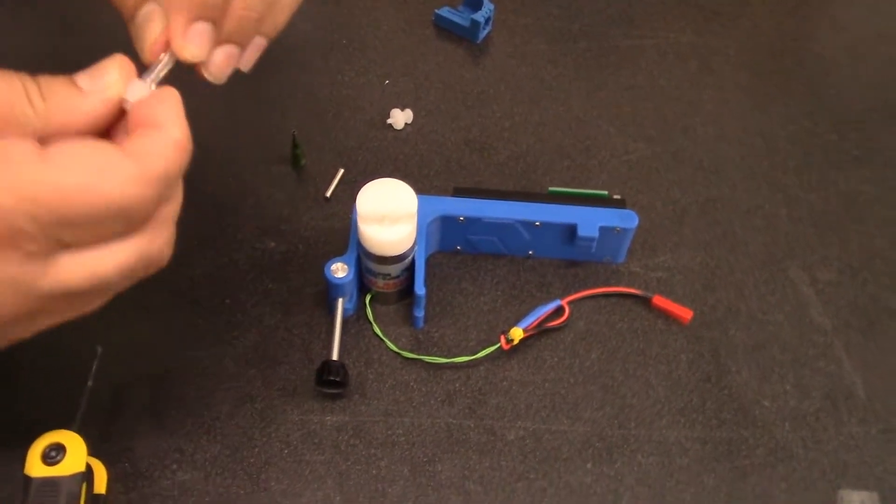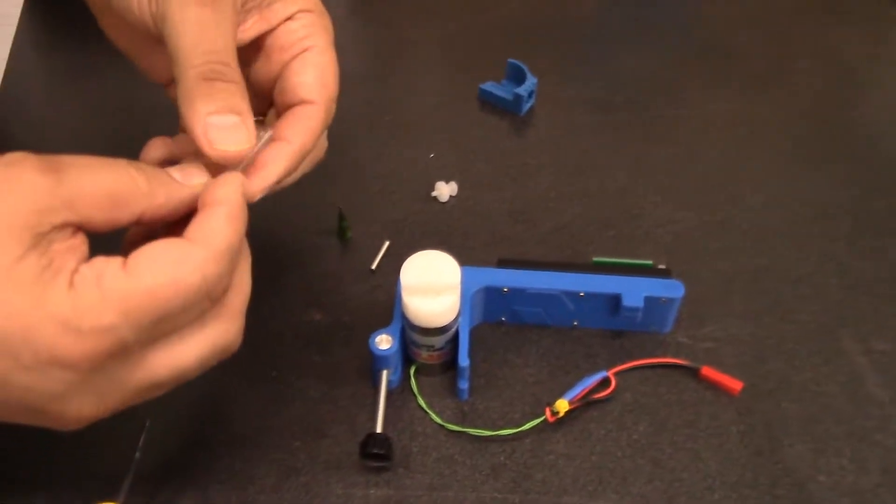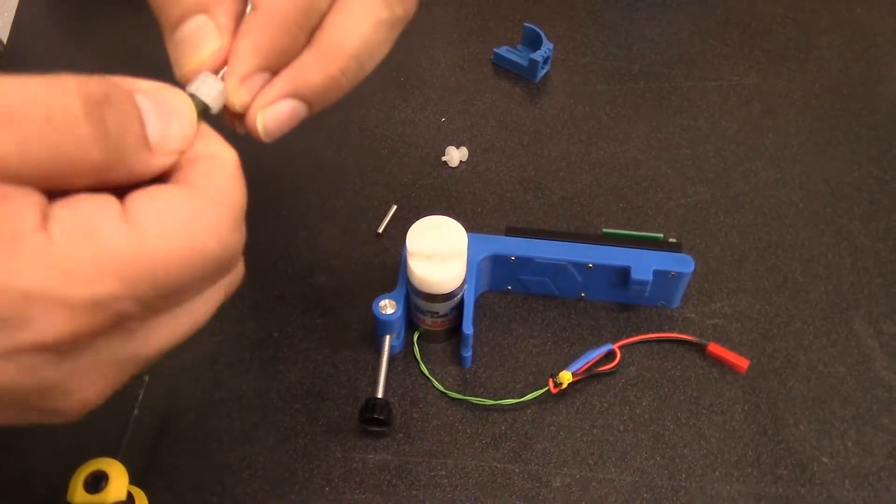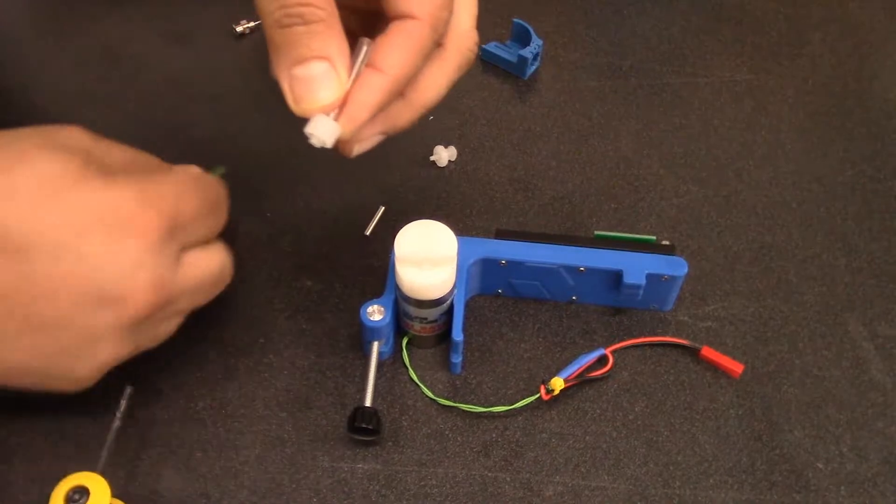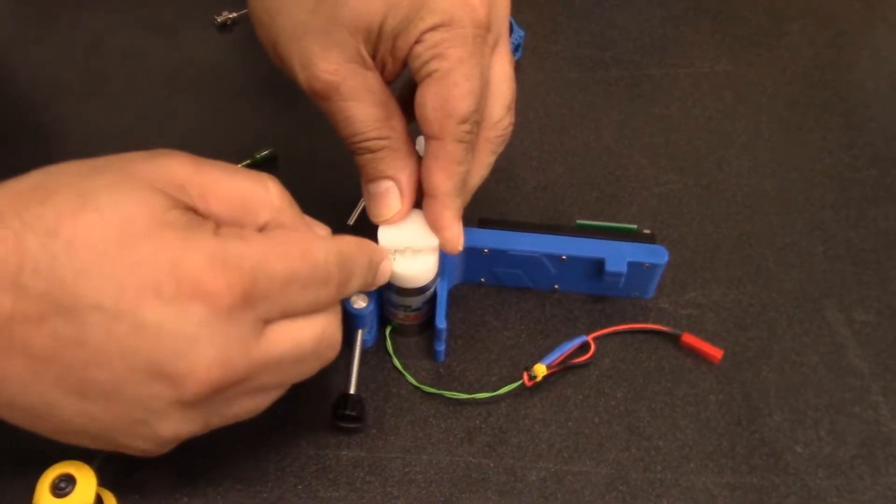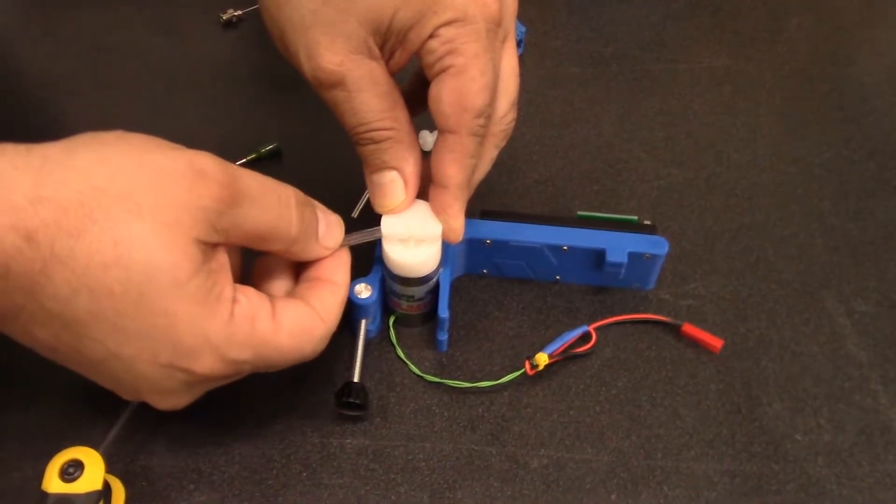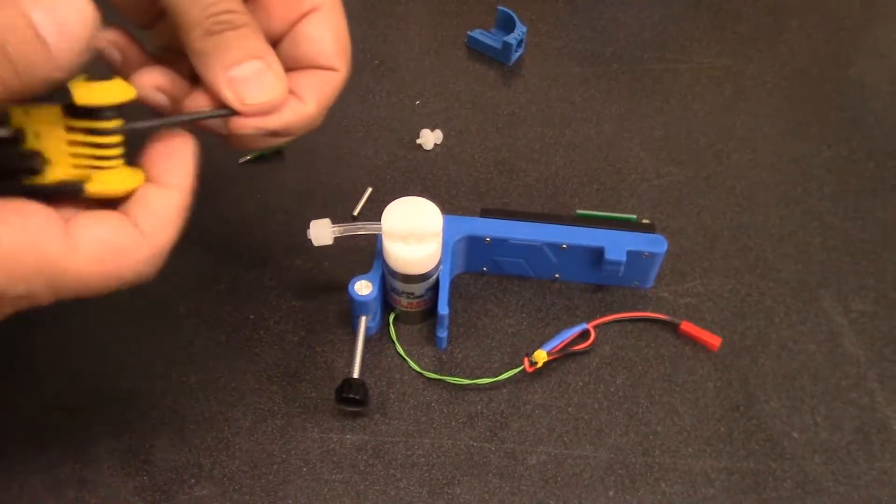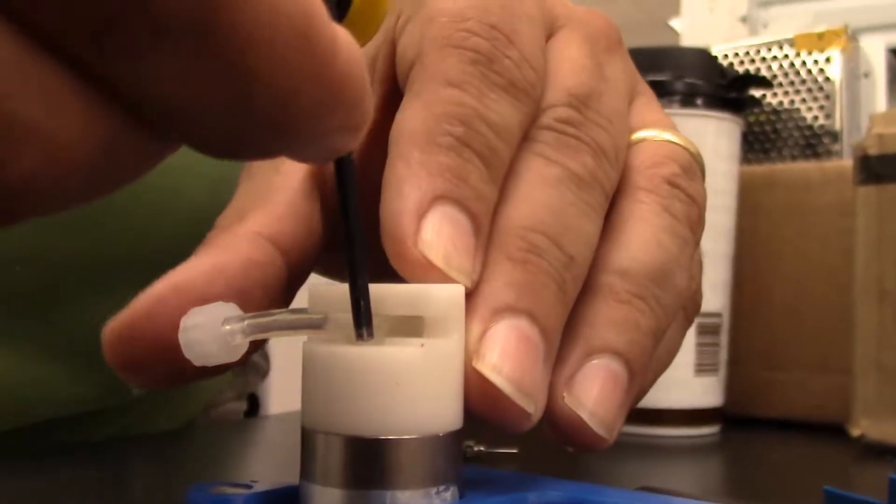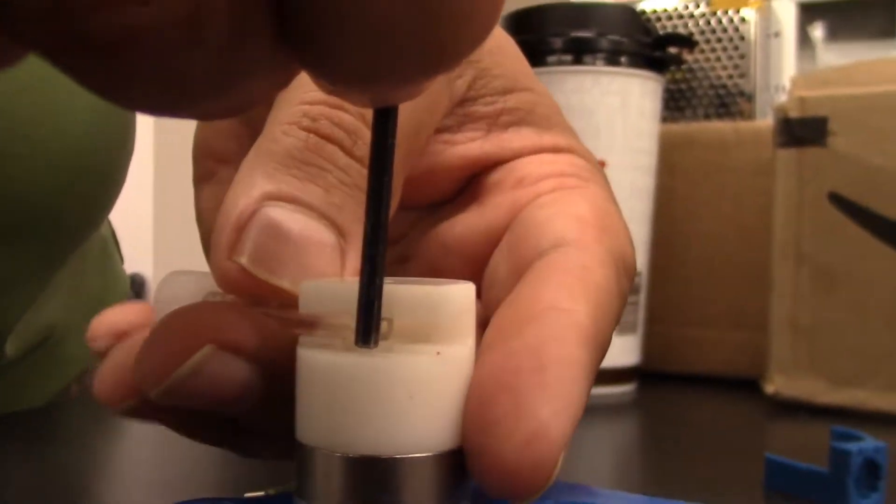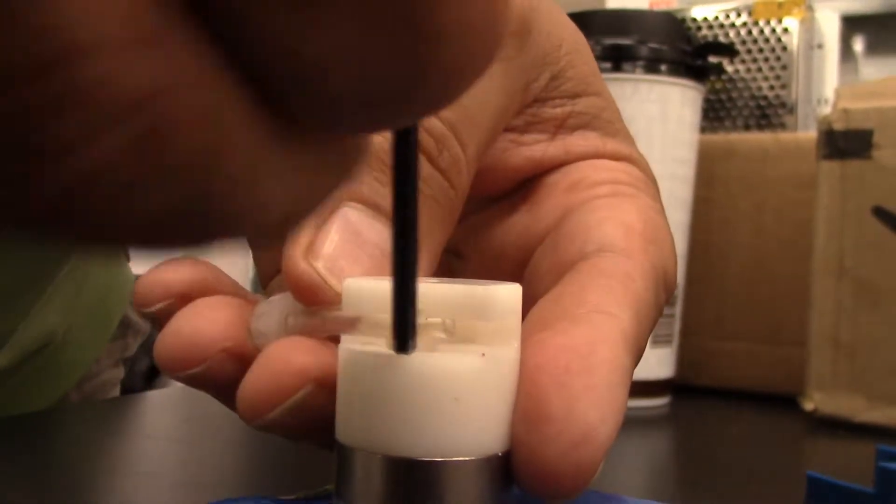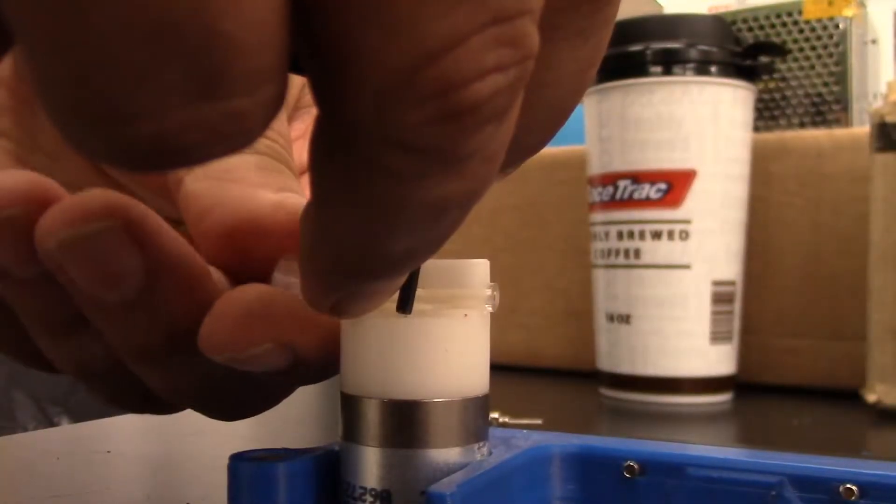Now to put it back in if you're replacing this tubing or whatever, we're going to want to leave the big connector that accepts your Luer needles on the bottom. You can't just stick it in from the front because this has got a keyhole shape so you have to come in from the bottom. You're going to want to push this plunger down and it helps if you rotate this a little bit as you slide it past. There we go.